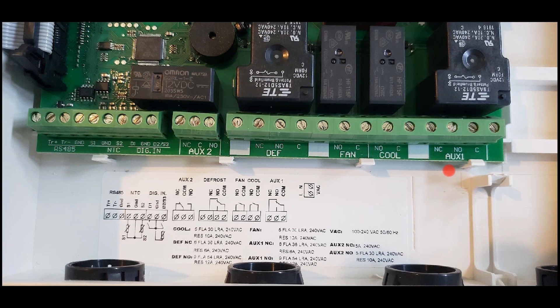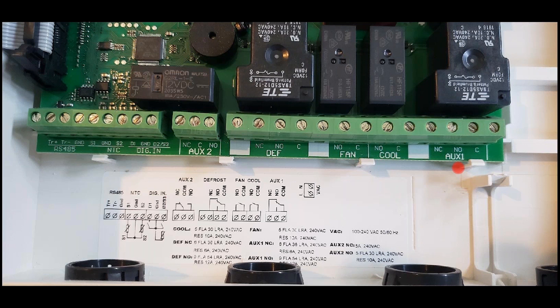Let's start with the first contact—auxiliary. This is exactly what it says. It's an auxiliary contact that, based on the programming parameter that you select, can be used to either start the compressor directly, or more commonly is used to power just about anything you want to turn off and on along with the call for cooling. If you want something to be on when the compressor is running, select the normally open contact. If you want something to turn off when the compressor runs, like a crankcase heater, then you can select the opposite contact, the normally closed.